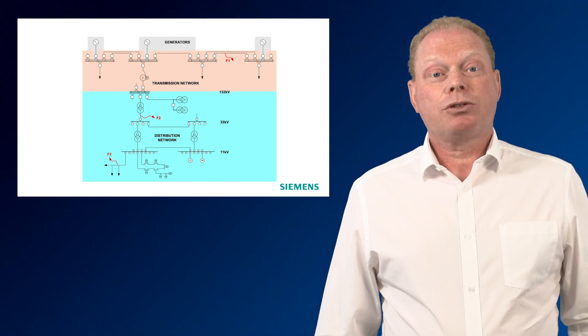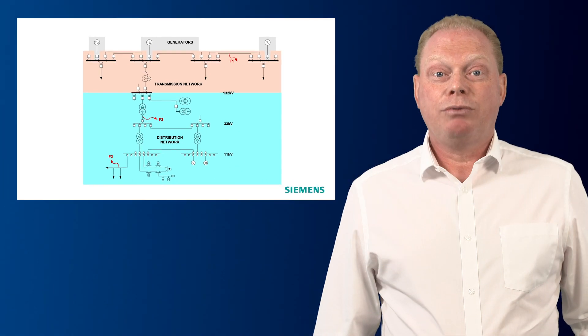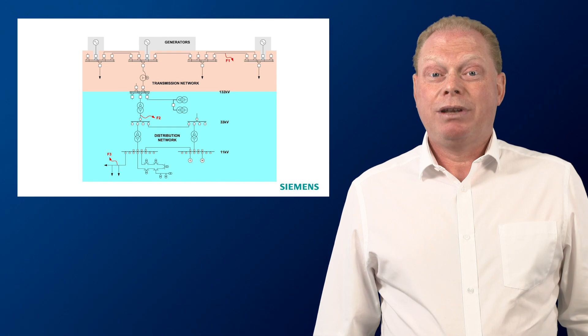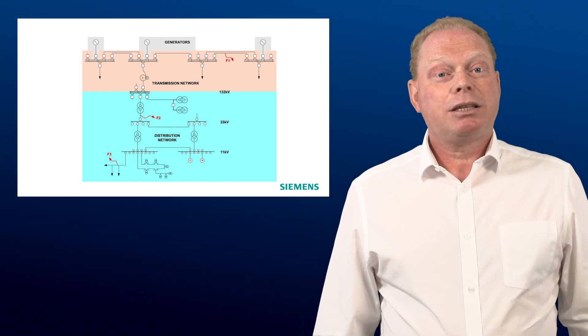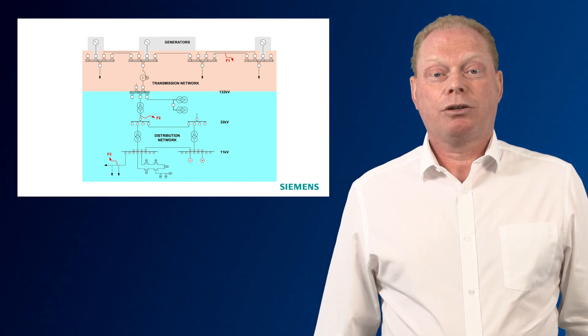The effect of faults on the network differ. Looking at this example, a fault at F1 will have very high fault power and is an important circuit as system stability may be compromised if a fault persists for too long. A fault at F2 will have high fault current but as there are alternate in-feeds available, it will have little impact on the network or customers. A fault on a radial feeder at F3 will have limited fault level but as there is no alternative source of supply, the loss of this circuit causes a loss of supply to the customer.